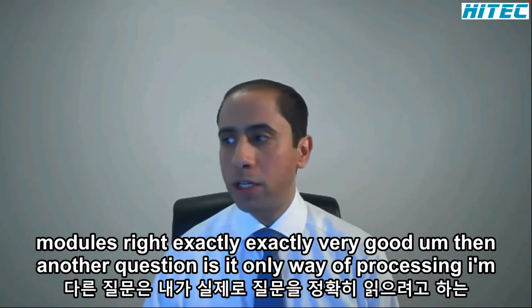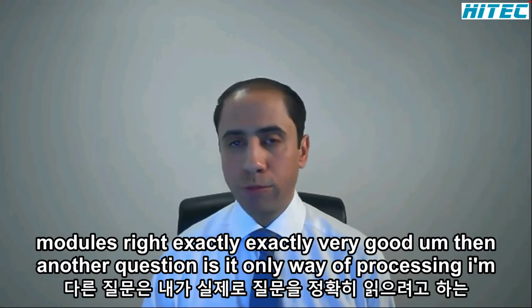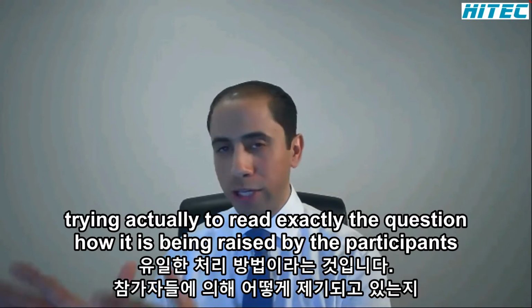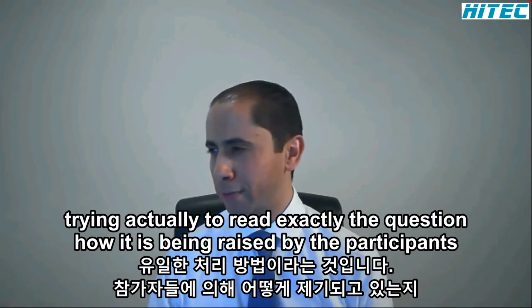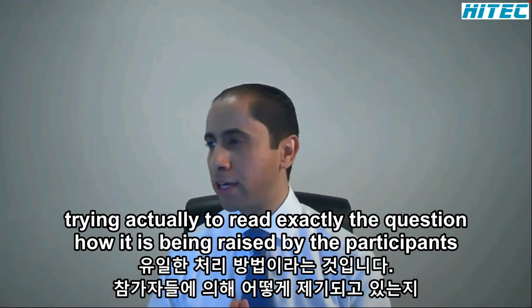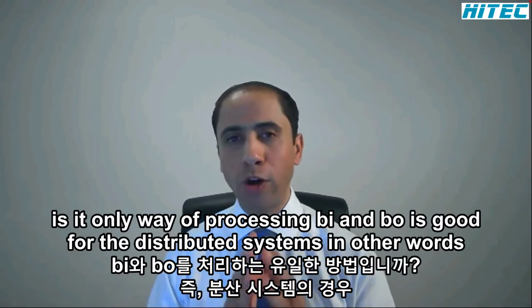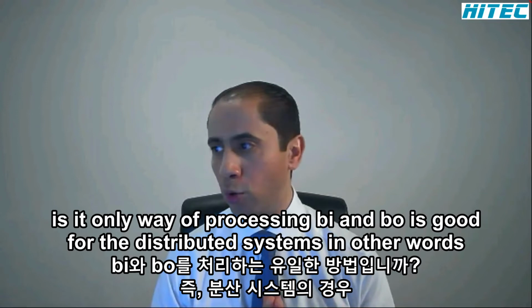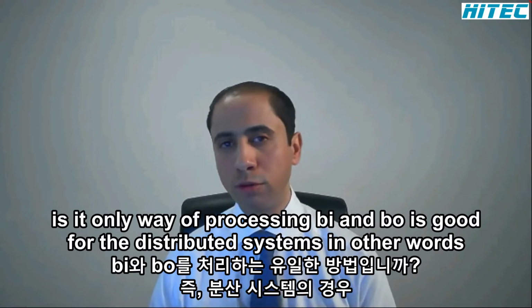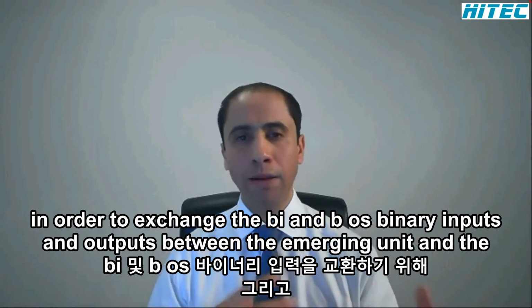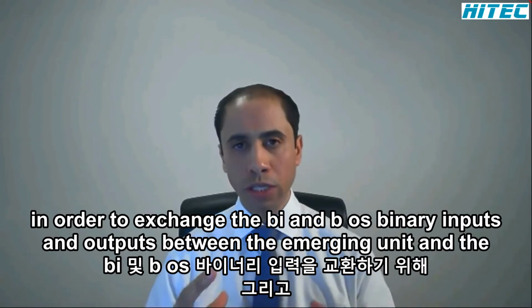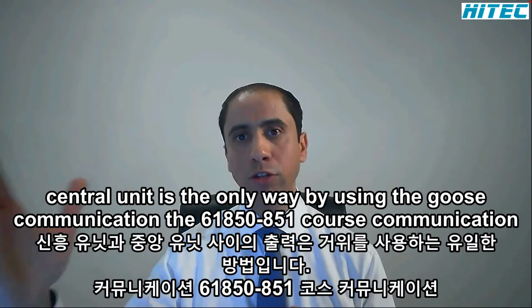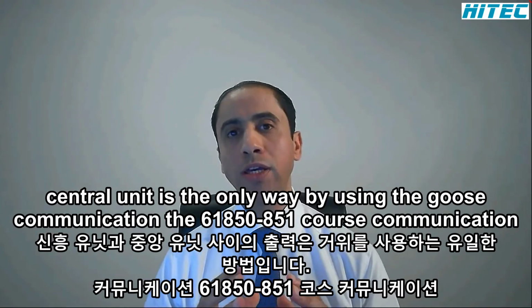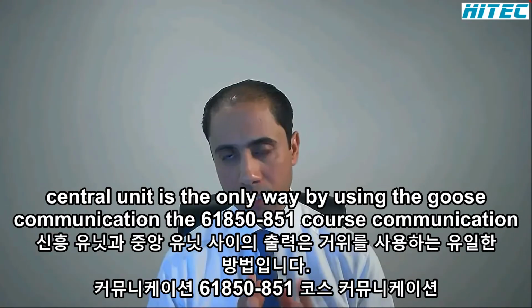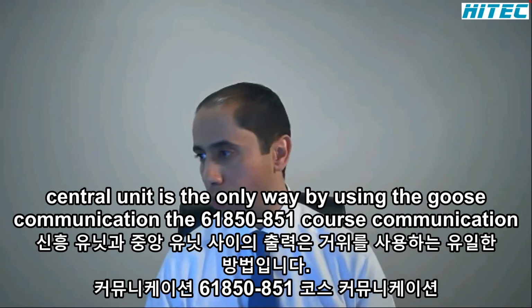Then another question. I'm trying actually to read exactly the question, how it is being raised by the participants. Is it the only way of processing BI and BO is GOOSE for the distributed systems? In other words, in order to exchange the BI and BO, binary inputs and outputs, between the merging unit and the central unit, is the only way by using the GOOSE communication, the 61850-8-1 GOOSE communication?